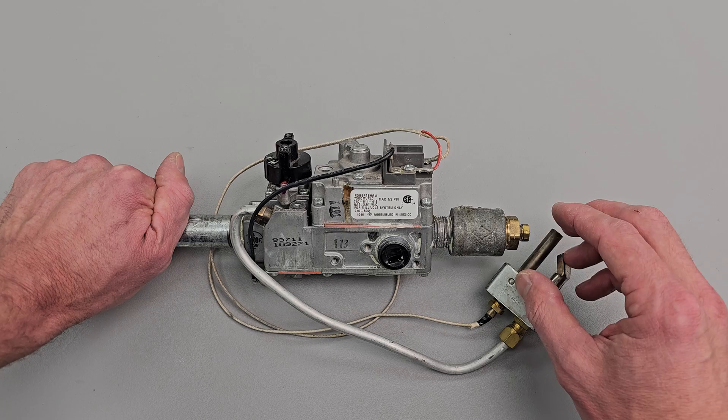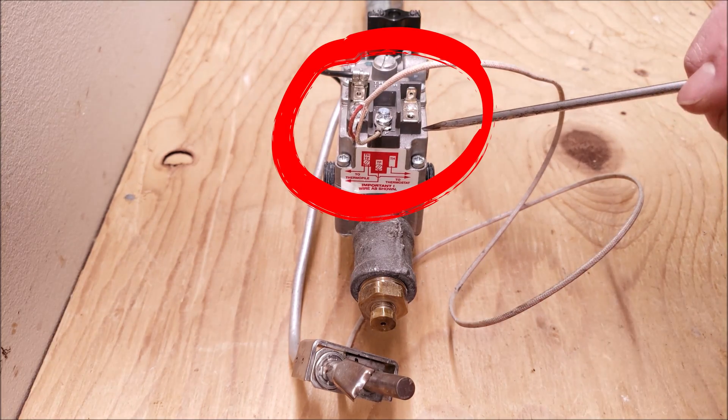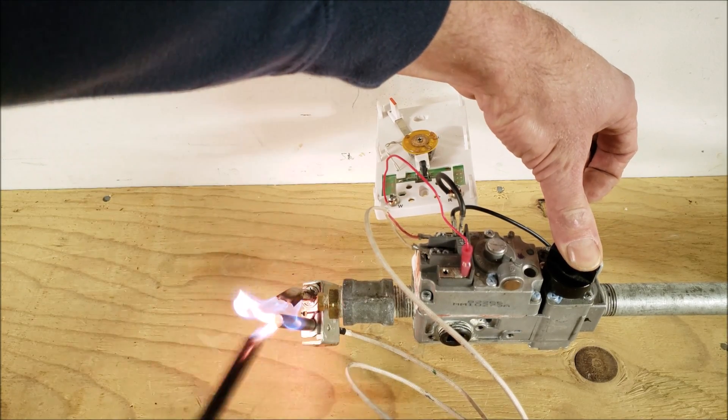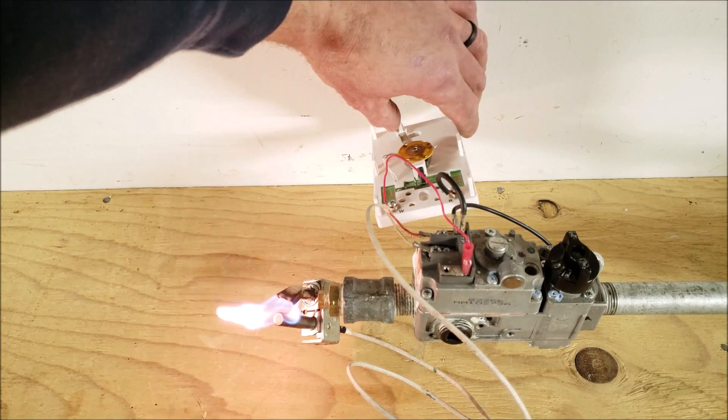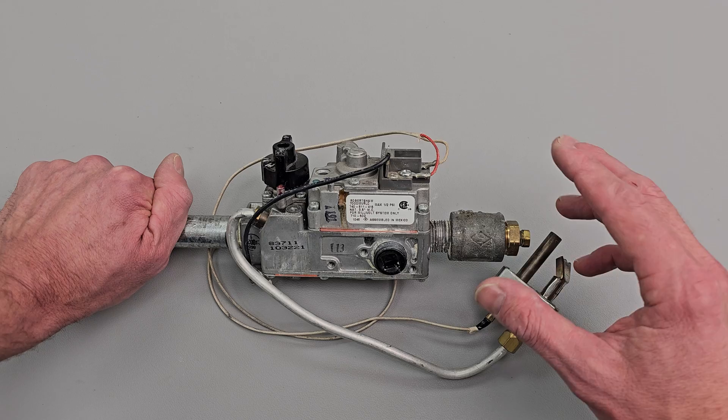You can take the power from the thermopile right here and apply it to the terminals back here, and that's going to open up the main stage to allow the gas to flow through to the main burners on a call for heat. There's no AC power applied to this gas valve, and this is found on older gas furnaces and some ventless gas fireplaces.